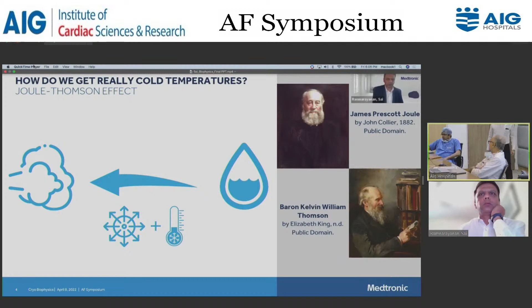We have pressurized liquid nitrous oxide, which is released to the distal portion where the balloon is located. Within the balloon, there are about 8 ports through which the liquid nitrous oxide comes out and expands to become gas, and during this expansion, the temperature drops to the boiling point of liquid nitrous oxide, which is minus 89.5 degrees centigrade. That's how we achieve really cold temperatures at the tip or at the balloon.